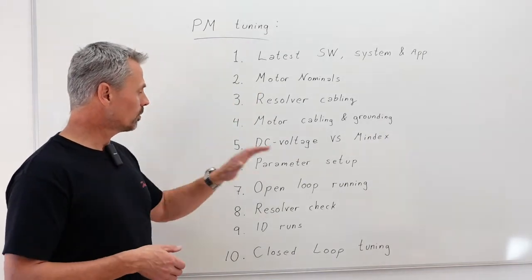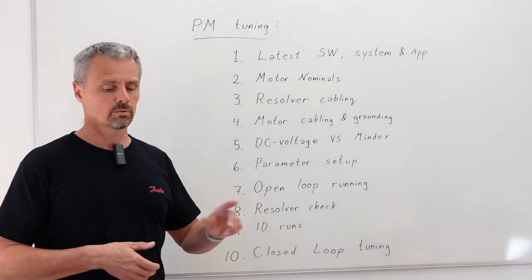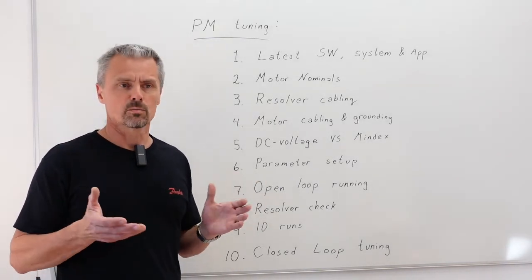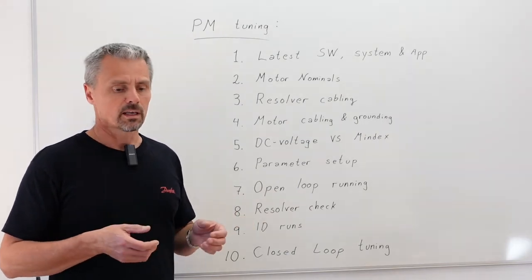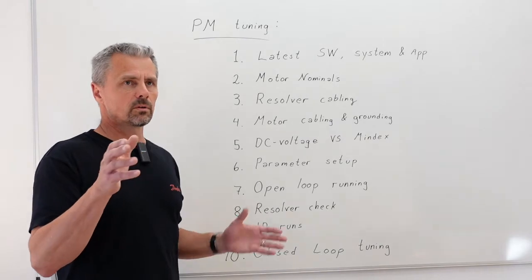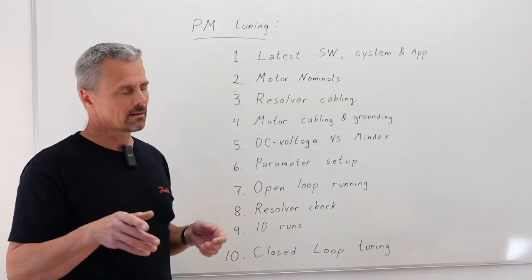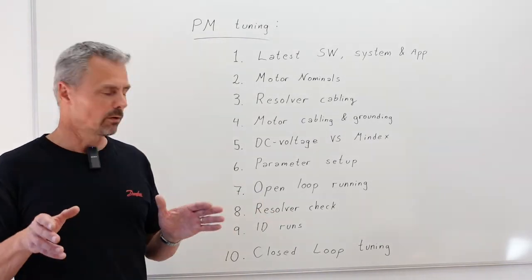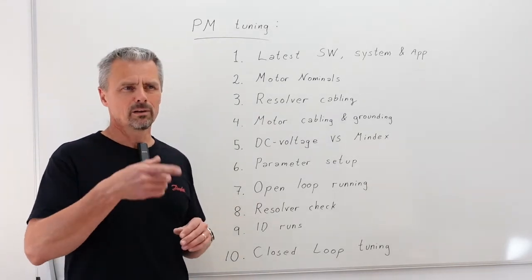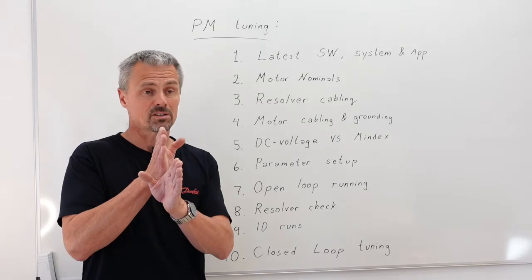Then we start running the motor in an open loop. Start very slowly, just listen to the motor that everything runs smoothly in case there is a gearbox or whatever. The shaft should be loose. Could the gearbox be on? Yeah, maybe. Preferably not but it's possible. Could a ship propeller be on? Well that should be flat pitch in that case.